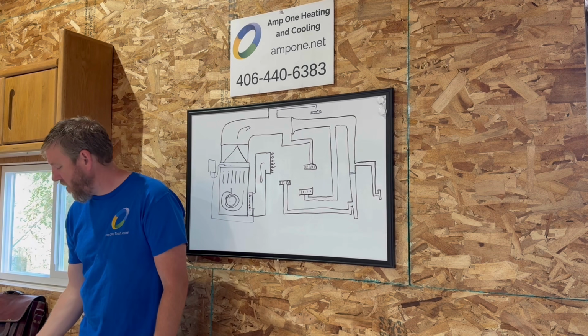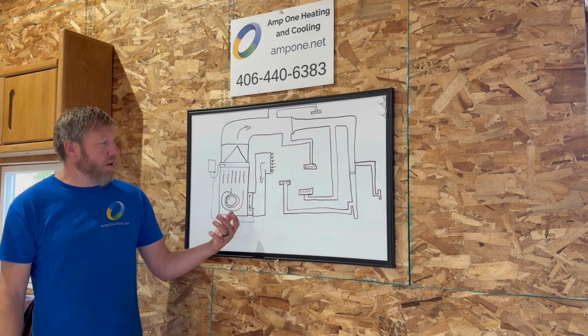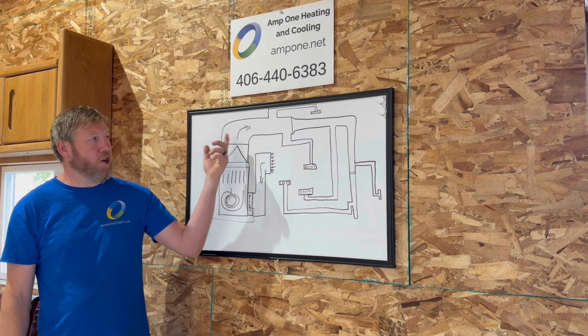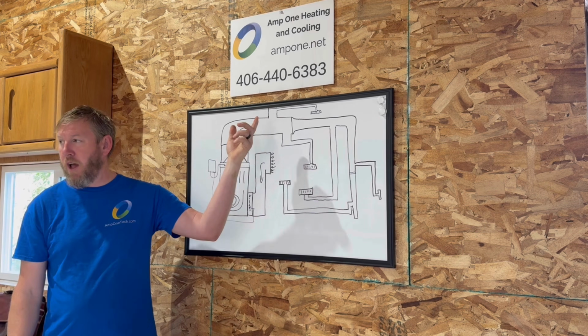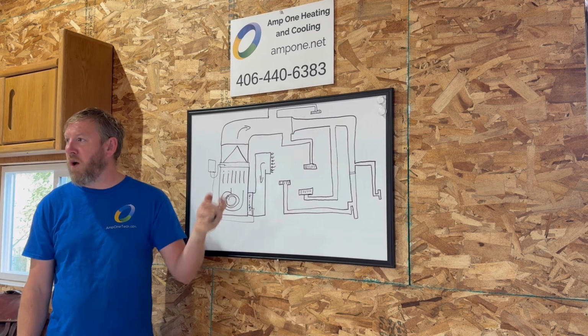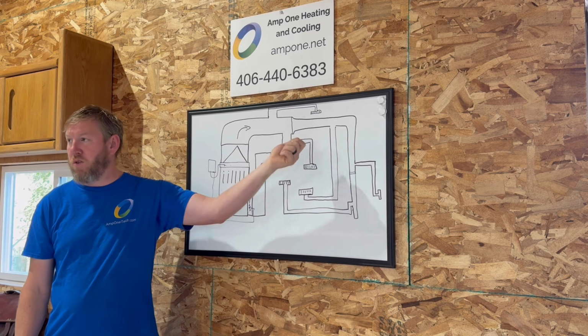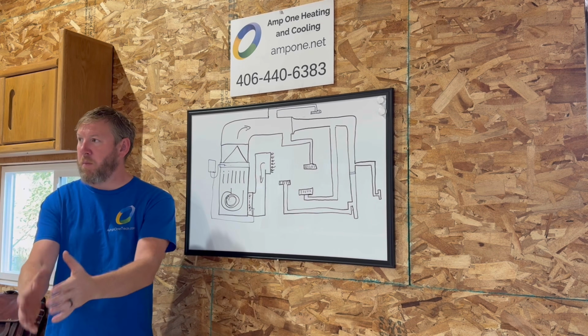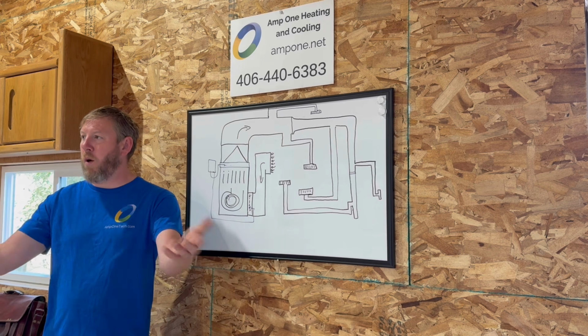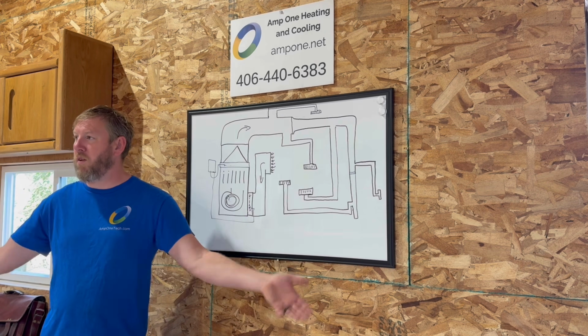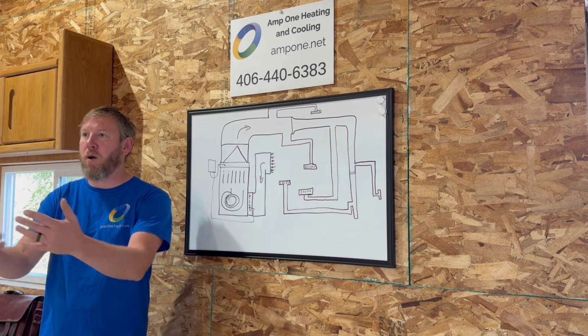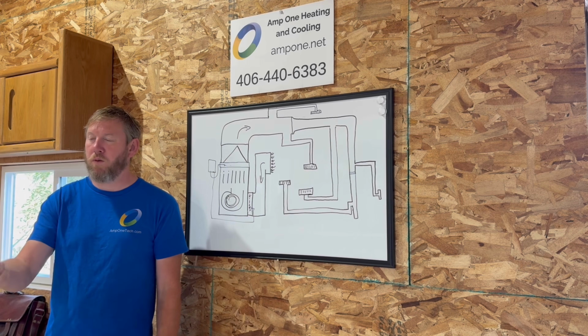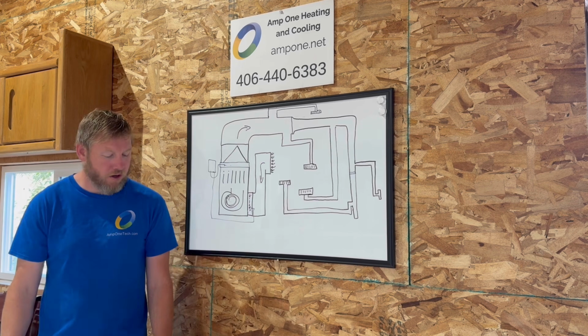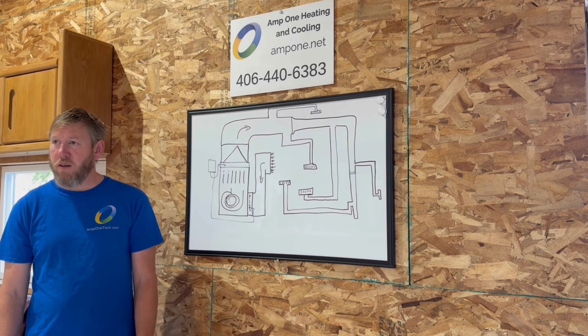So, airflow is a big deal, and there is a formula to check how big your duct size is, how many runs you can take off of each one, and then how much to reduce it down to, so that each time it steps down, you're keeping that airflow up, because you're just robbing airflow to keep the pressure up. You know, like putting your finger over a hose keeps that pressure up. So, any questions on that?